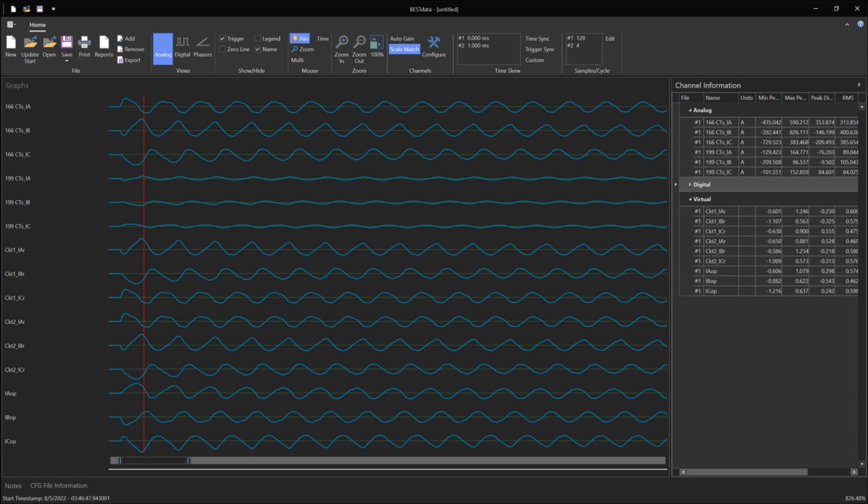This one we're going to be looking at how to use virtual channels to calculate differential currents and to find both operate and restraint current of a differential element. This type of math can be used for lots of different things. Differentials just happen to be one of the places where relays use a lot of internal math functionality in order to normalize and balance things out and create predictable protection.